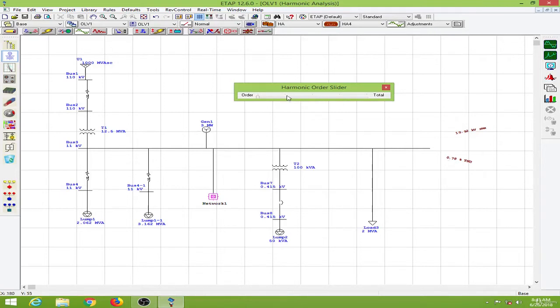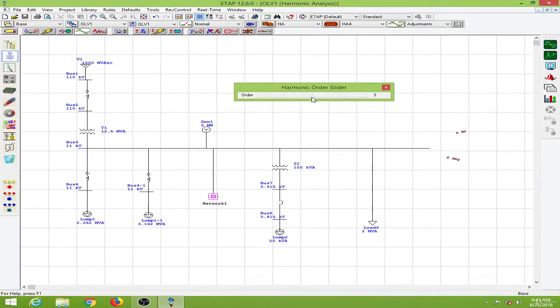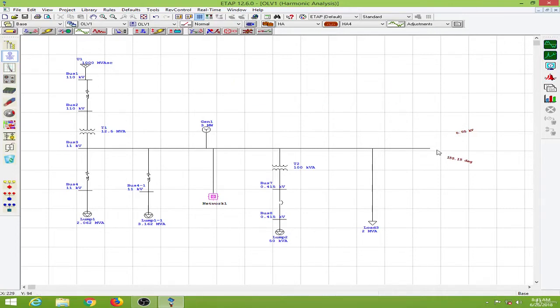And when I slide the harmonic order, this is the first harmonic, that is about 10.92 kV. There is no third harmonic, and the fifth harmonic is 0.07 kV. And this is the seventh harmonic. Since the harmonic value is below the specified limits...